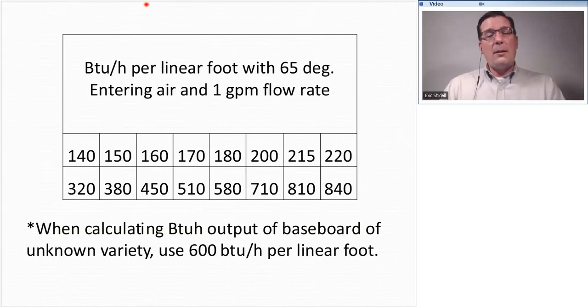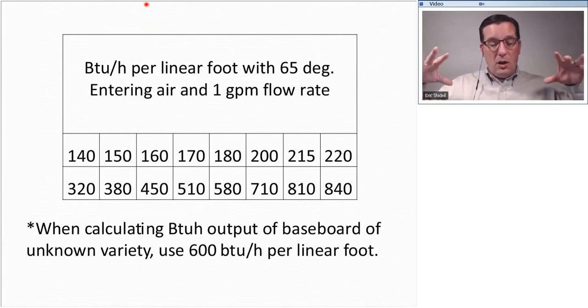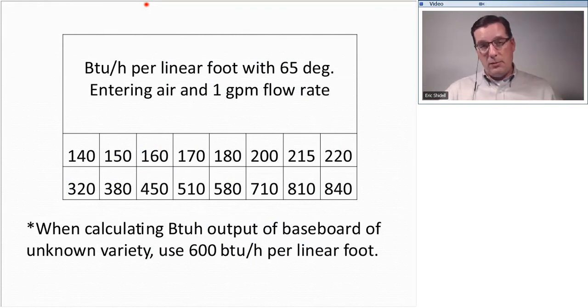Now, a copper fin baseboard is a heat emitter, and a lot of the time when sizing boilers, a lot of folks are going to go along and measure all the baseboard in the house, assign a heat output for that amount of baseboard, and size the boiler based on that. And that isn't always the best way to go. It's much more effective to size the boiler for an actual heat loss calculation for the house and then adjust the water temperature to accomplish what we need to accomplish.